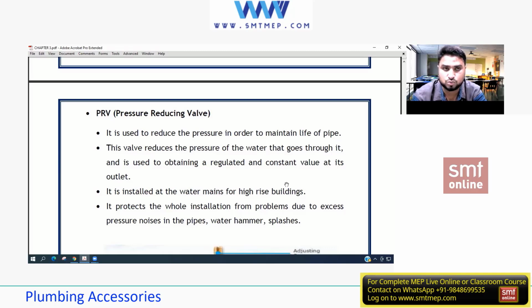But the problem occurs when the pressure is coming down, it increases more and more. As per the standards or codes like IPC and UPC, it should not increase more than 80 psi and 60 psi. So 80 psi is set by IPC and 60 psi is set by UPC. Whatever standard your company is following, whether IPC or UPC, you need to check in the riser, in a vertical pipe in short, that the water which is coming down should not exceed it.